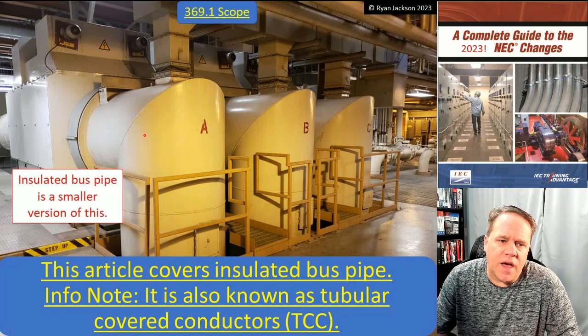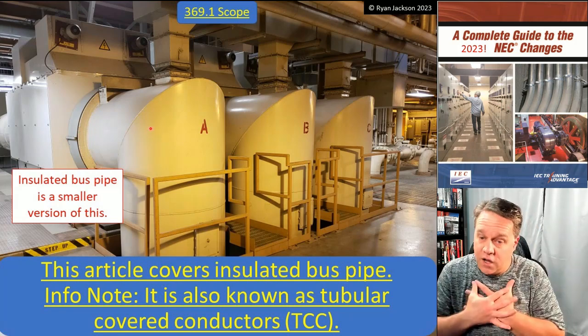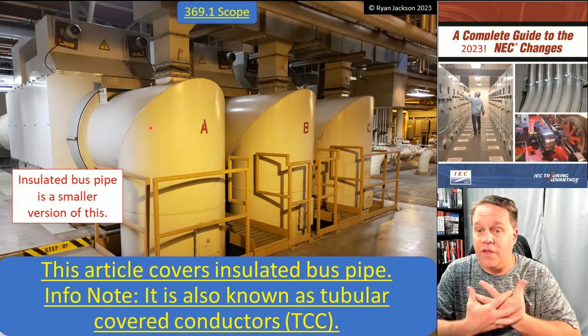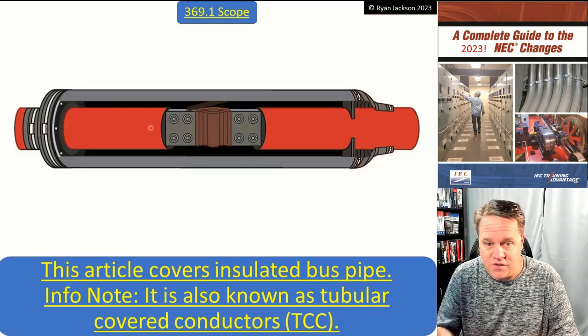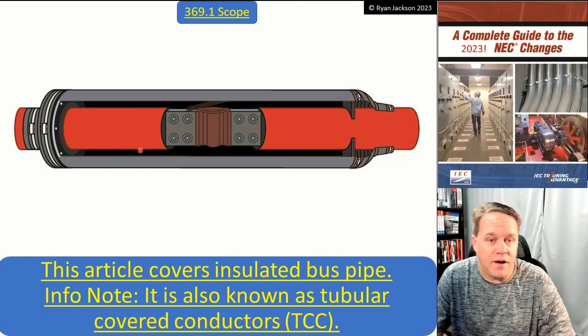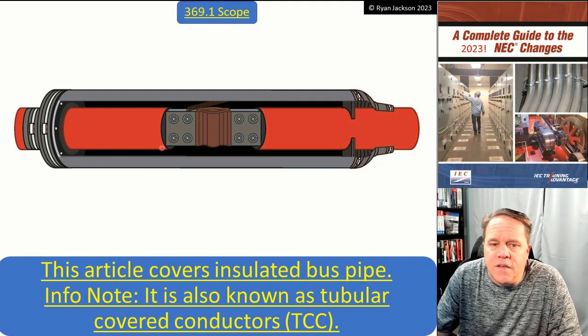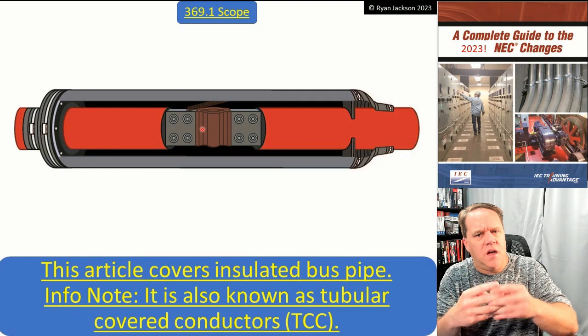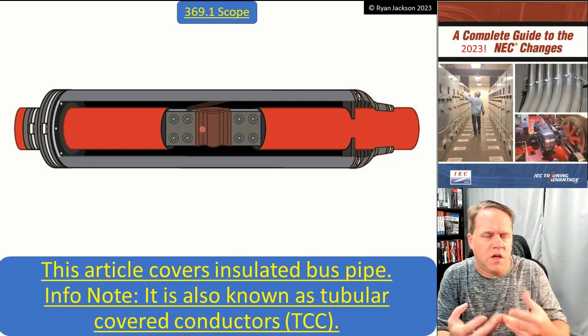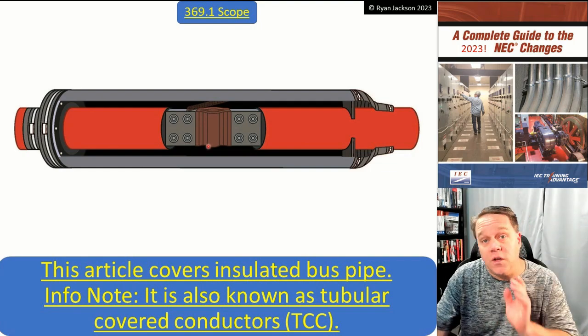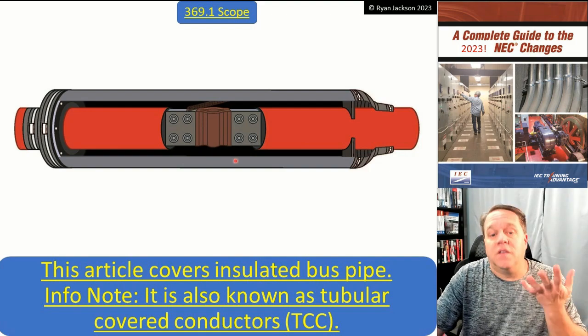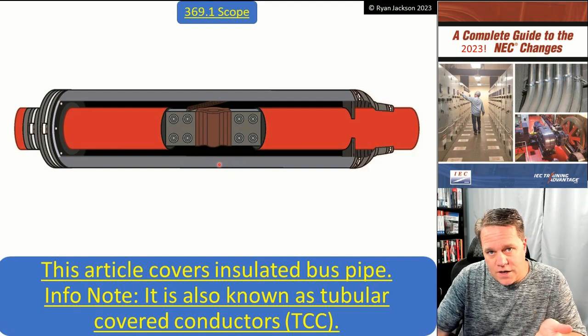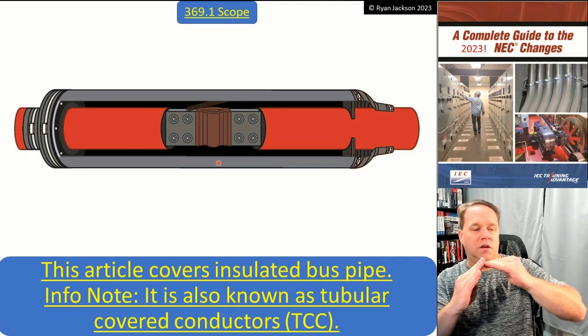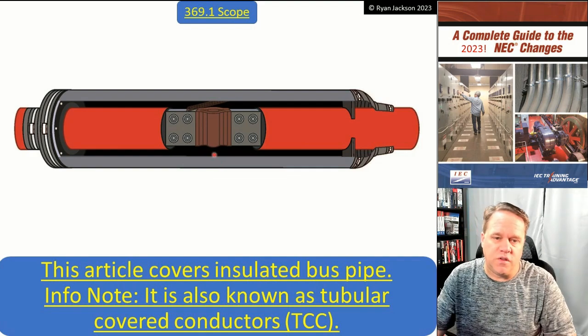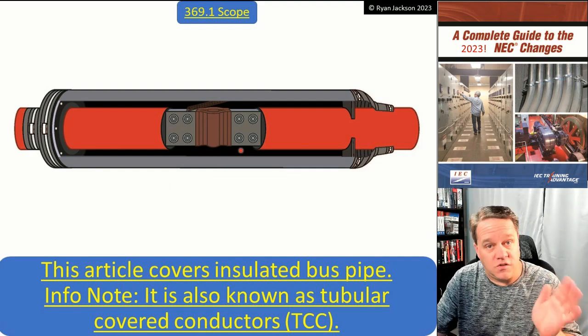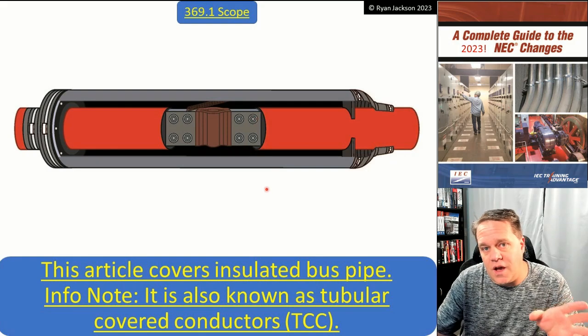So what they have here, in the NEC version, is the insulated bus pipe. It looks like this, a smaller version of that. You've got these bus bars inside of the duct, and they get bolted together at certain intervals. This allows you to change directions. If I'm going 90 degrees, you can do it with this joint right here, and that's what you're going to see in an Article 369 application.